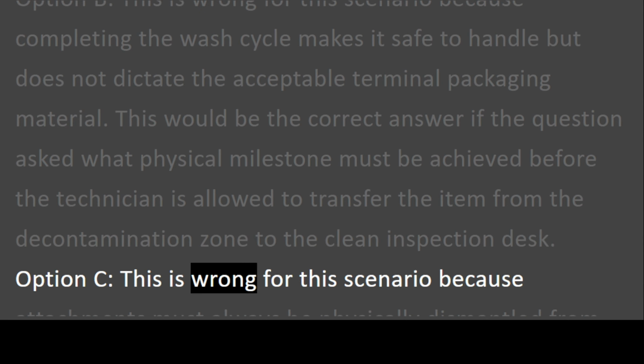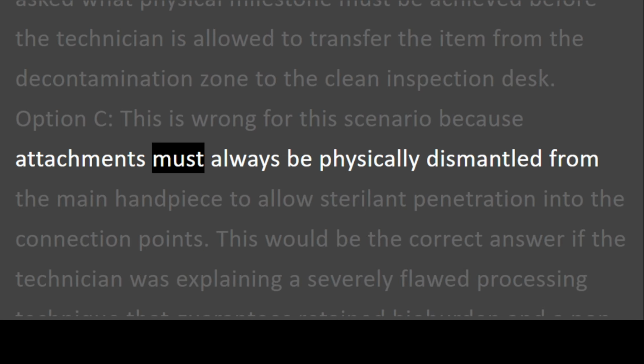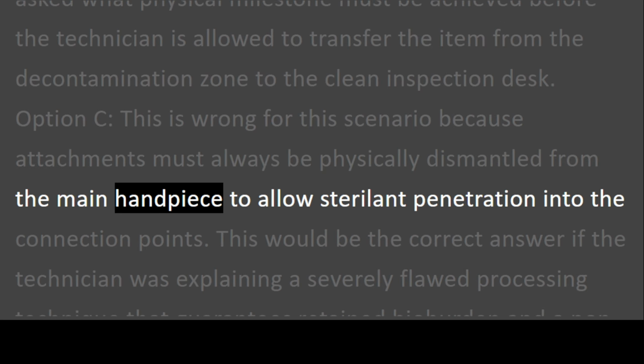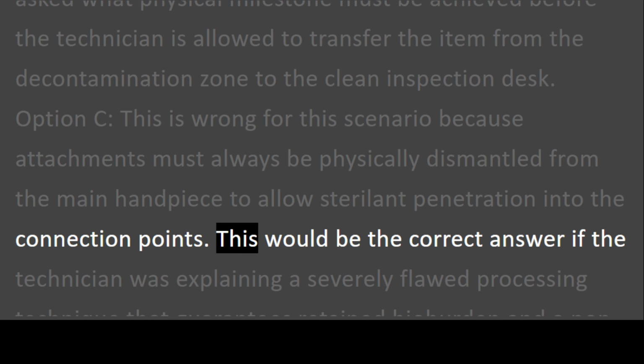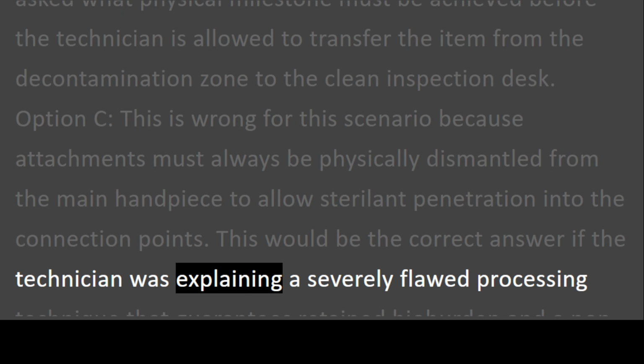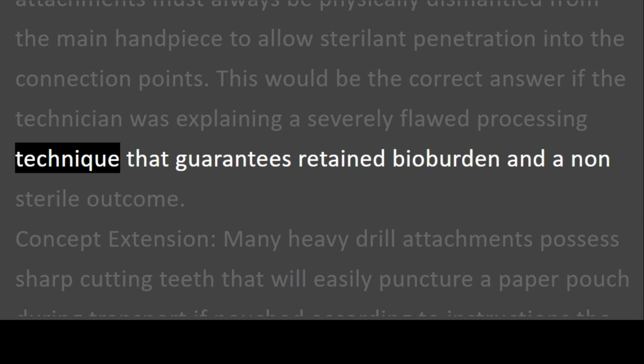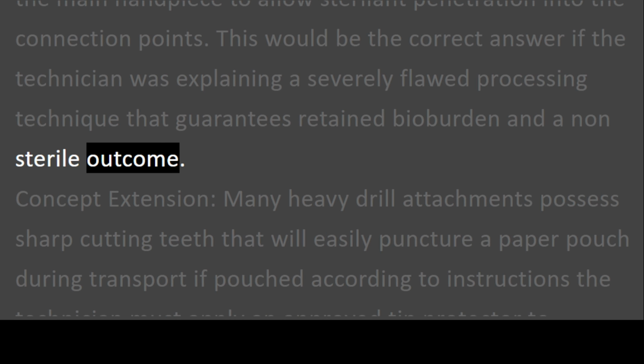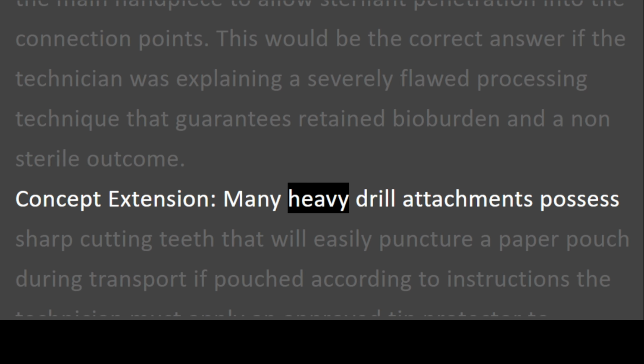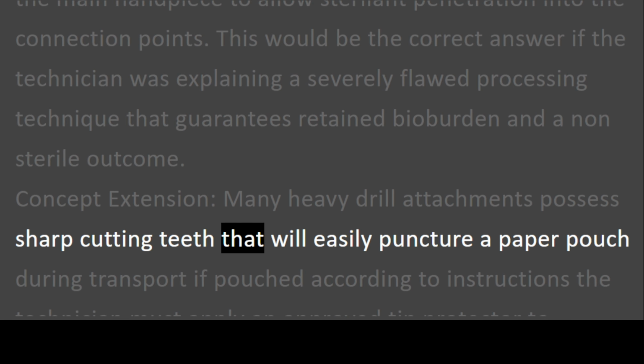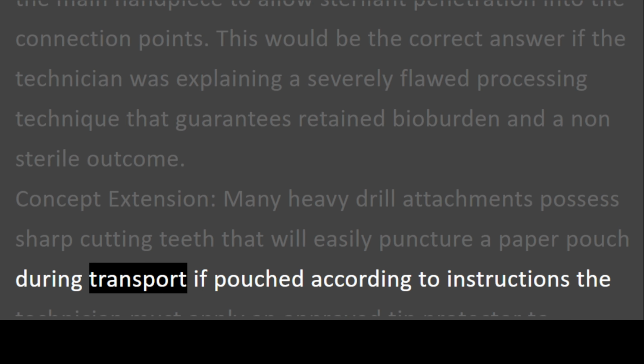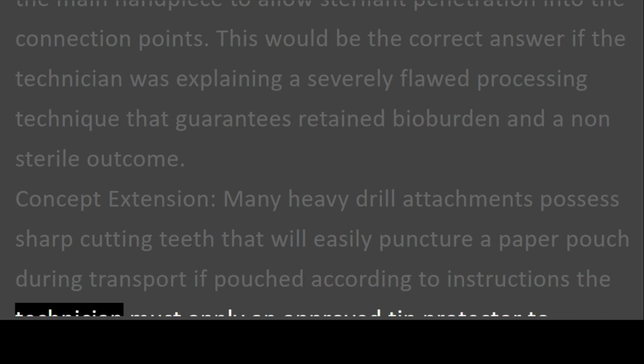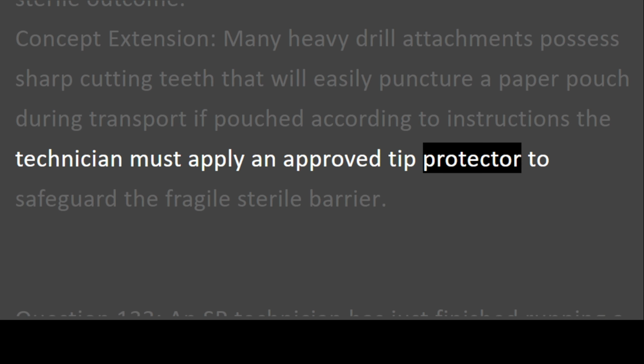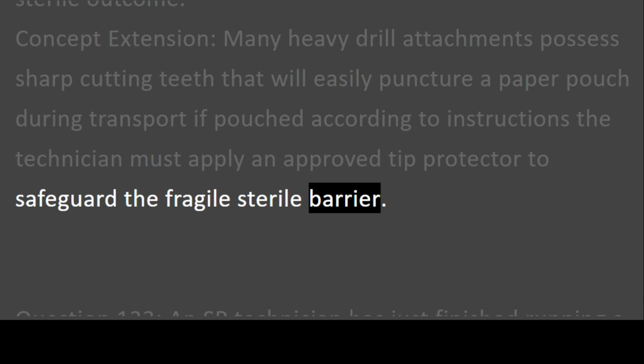Option C. This is wrong for this scenario because attachments must always be physically dismantled from the main handpiece to allow sterilant penetration into the connection points. This would be the correct answer if the technician was explaining a severely flawed processing technique that guarantees retained bioburden and a non-sterile outcome. Concept extension. Many heavy drill attachments possess sharp cutting teeth that will easily puncture a paper pouch during transport if pouched according to instructions. The technician must apply an approved tip protector to safeguard the fragile sterile barrier.